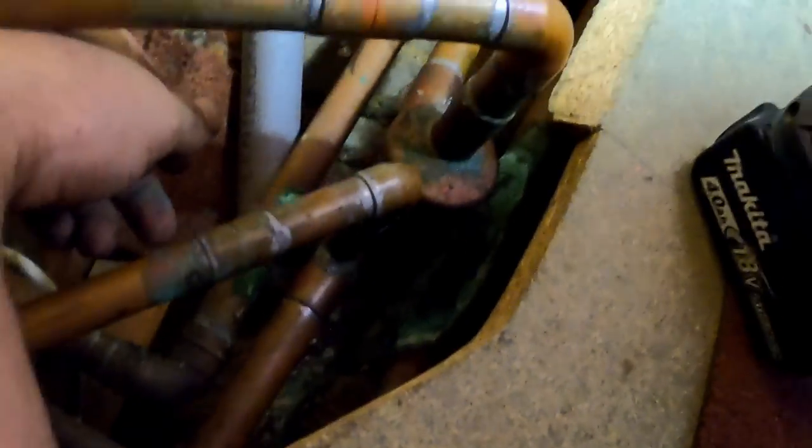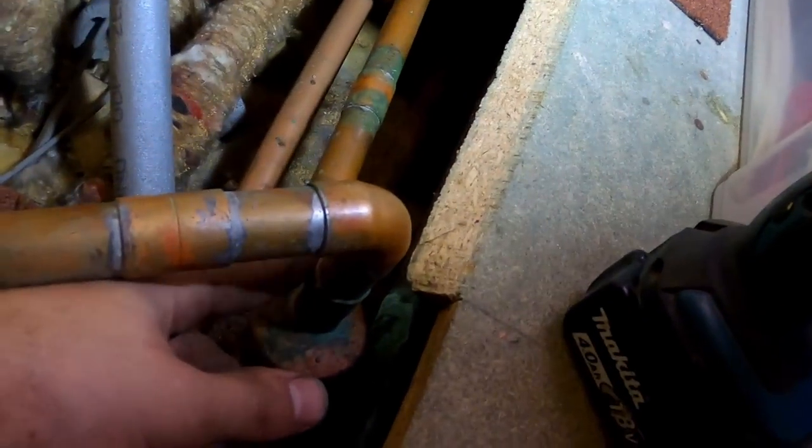That pipe next to it looks pretty manky and old, doesn't it? God knows what that is. I wonder what that is. I don't know, I'll have a look at it. Looks like it's been leaking, doesn't it? I bet the air sep's been leaking, to be fair, and it's leaked that much, it's blocked up, and then it stopped filling the system. What I'll try and do, I'm just draining it from the boiler again. I hate air seps, I do. But yeah, we'll get it cut out and get it sorted.